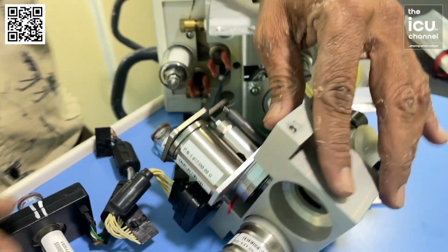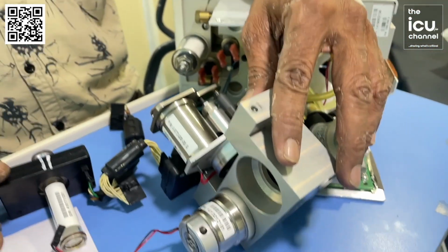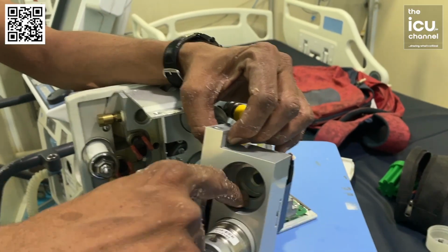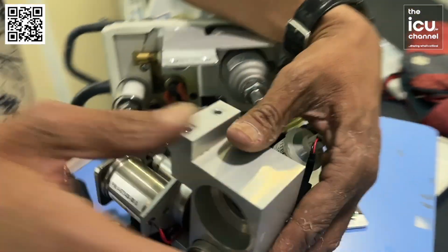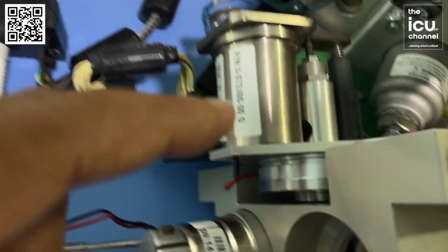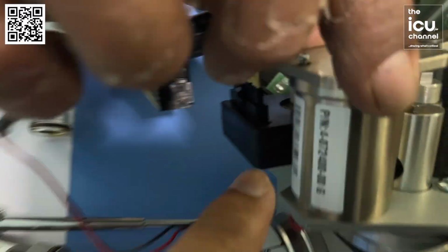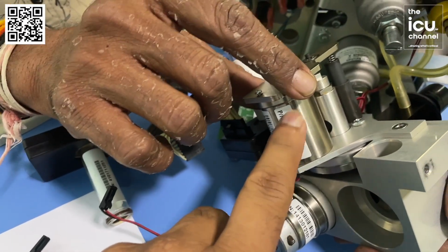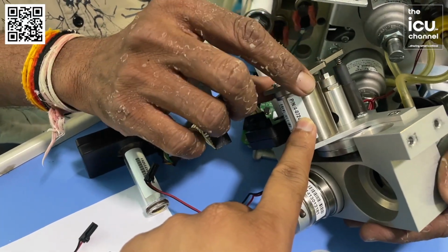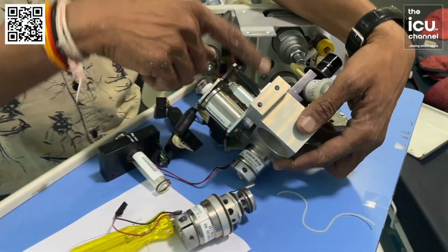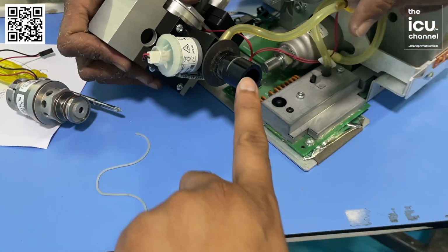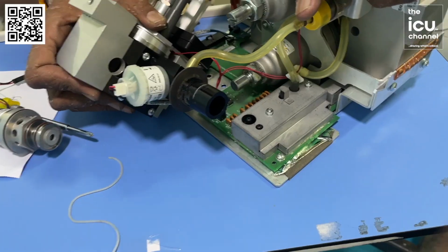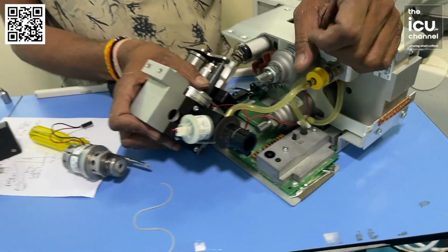Suppose we have set 30% FiO2, 50% FiO2, 100% FiO2. Based on the settings, they will adjust the proportions of air and oxygen and then deliver it to the patient. So it is here where it is done. After the medical air and the oxygen get mixed, both of them pass from the mixer to this safety valve. This safety valve again checks whether the correct amount of tidal volume is getting delivered or not, or the pressure is correct or not, and from there the mixed air, the set amount of FiO2 with pressure, is delivered to the inspiratory limb. From there the inspiratory limbs get connected, and this is delivered to the patient.